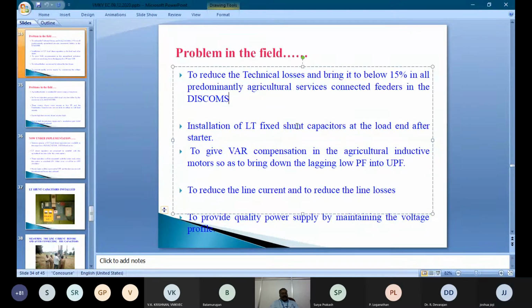So all the industries install shunt capacitors or automatic power factor correction. Many shunt capacitors are available, and they are added automatically to the motors depending upon the average power factor. But in agriculture, there are no such capacitors, provided either by the utility or by the consumers. These motors always run at a very low lagging PF and cause huge losses to the utility.